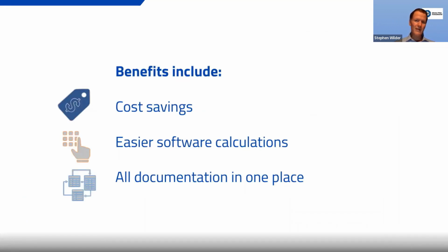It's easier to have all the information in one place. It's easier to create safety training material when you have a single document to refer to. The arc flash calculation, in a way, is a combination of short circuit and coordination. If during the coordination study you decide that you should change a breaker setting, it'll change your arc flash values. And if a panel is determined to be inadequately sized for a short circuit study, it'll need to be replaced, which also affects the coordination and the arc flash study.